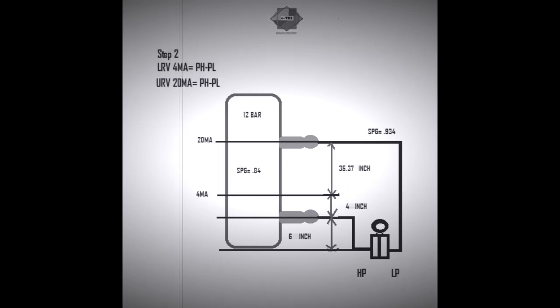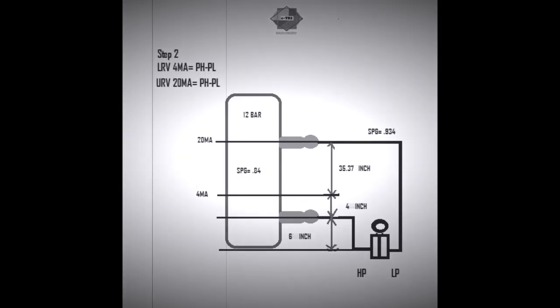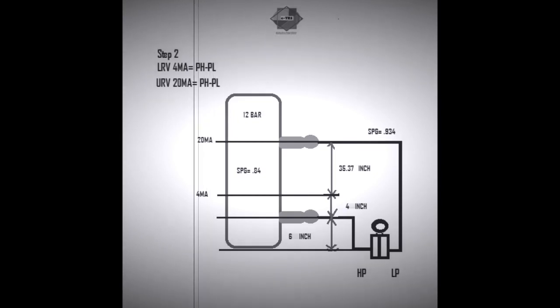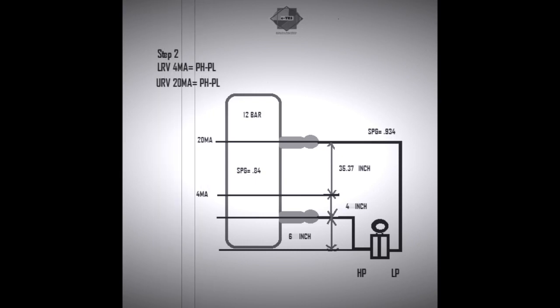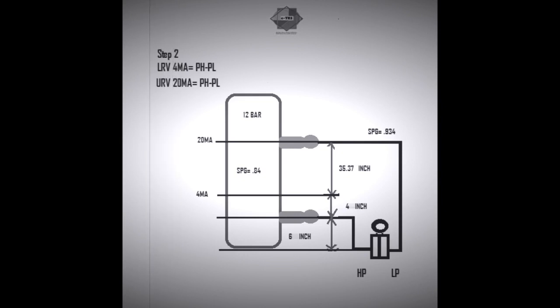The LP side tapping point 100 percentage level is 35.37 inches above the zero percentage level. Now we are going to find LRV and URV. The formula for LRV is PH minus PL, and the same formula is applicable for URV. The difference is LRV is used to calculate 4 milliamps and URV is used to calculate 20 milliamps.